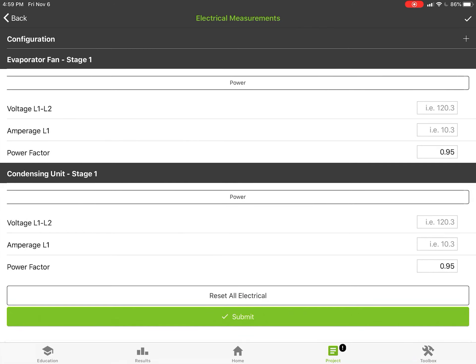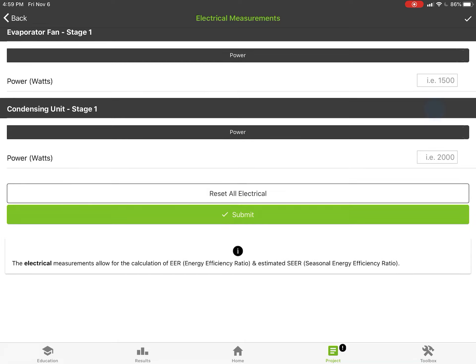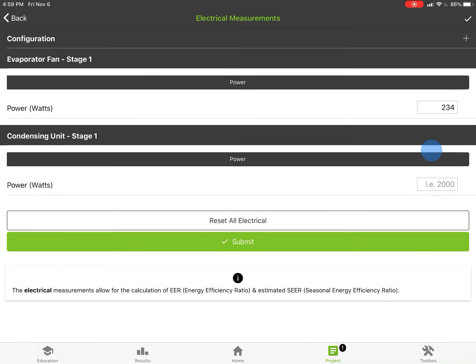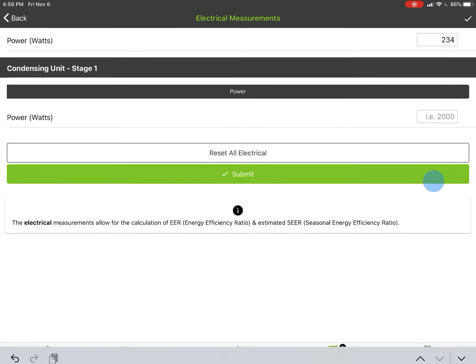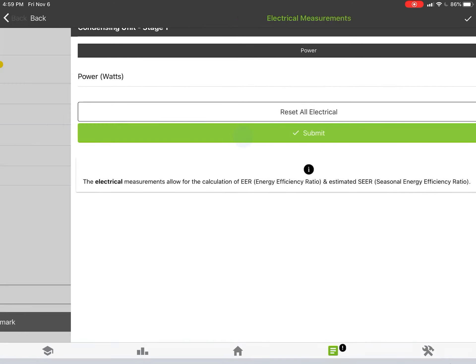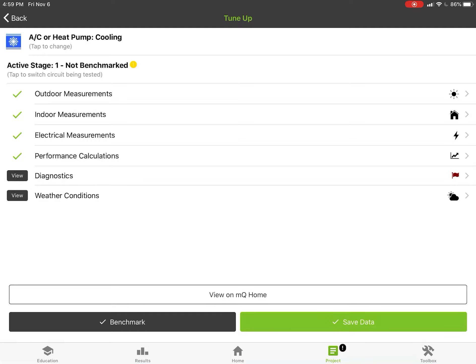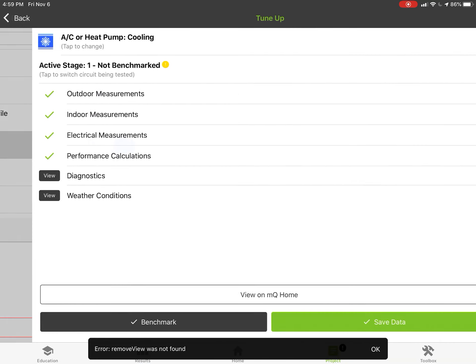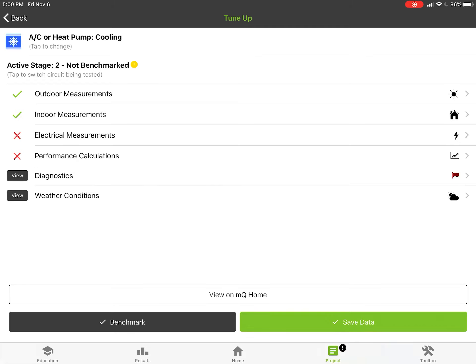But it does clear your electrical measurements out for each stage independently. I'm gonna go with power with both of these here. We'll just say it's 234 and 1090, tap it again here, 1090 and hit submit. That would be my first stage and I'd save that data. Then I'd go ahead, dismiss or go back into measurements, and when I go to my second stage you're gonna see my electricals cleared out because now it's expecting a new set of electrical readings. Then I just move over my outdoor and indoor probes and get my second stage on there.